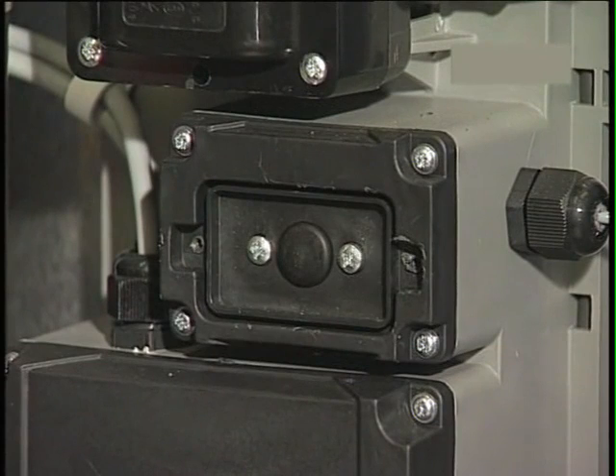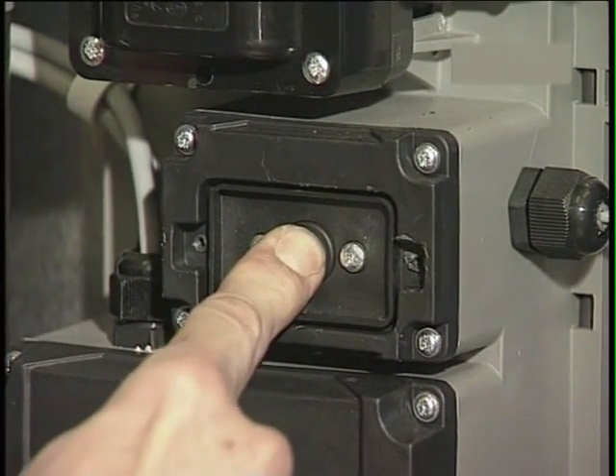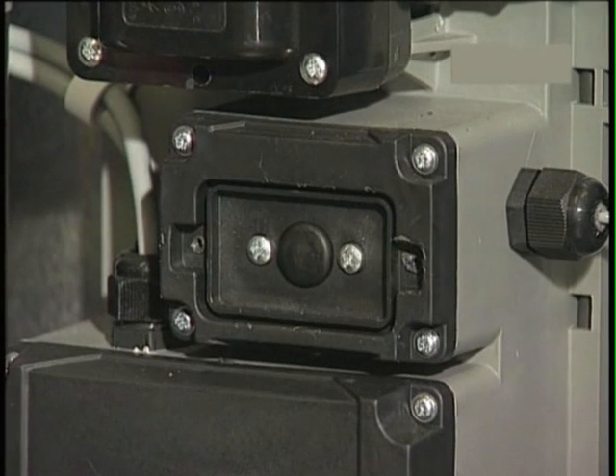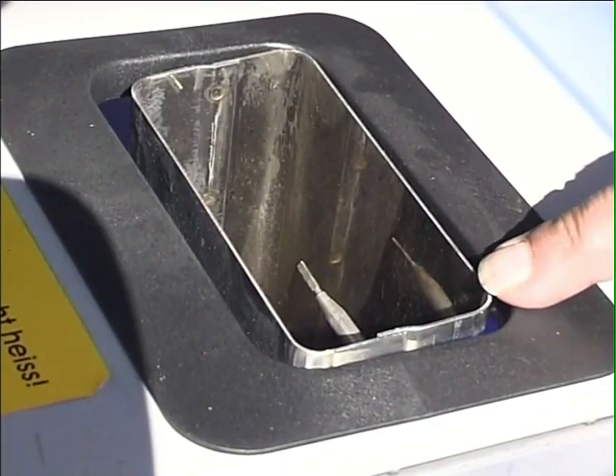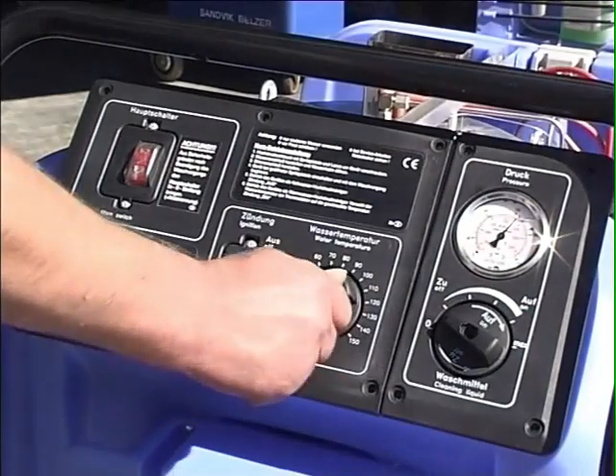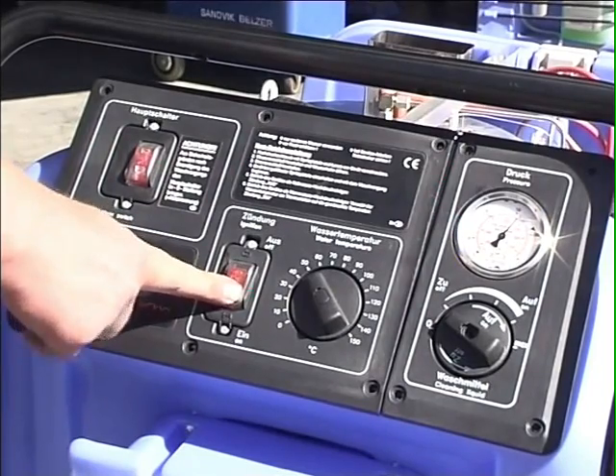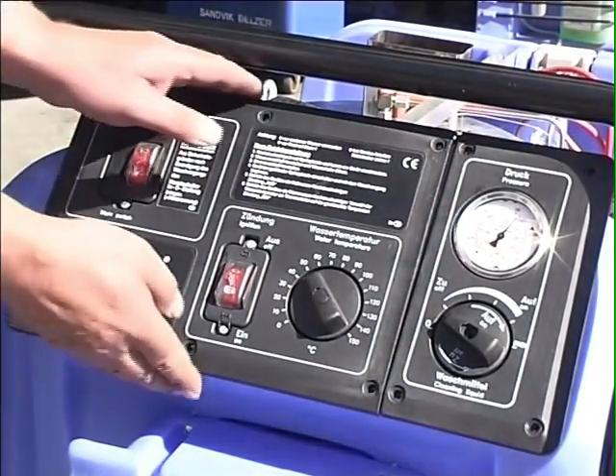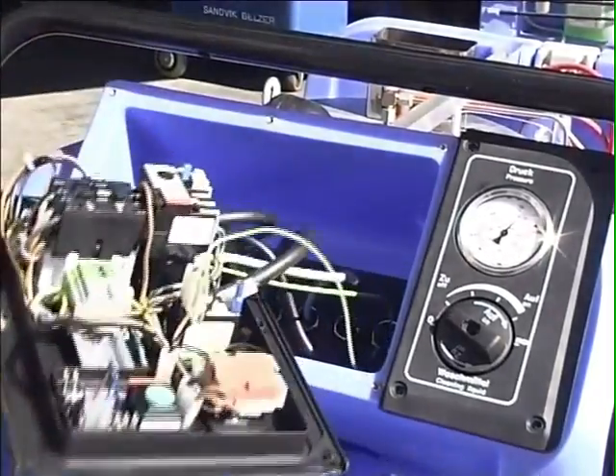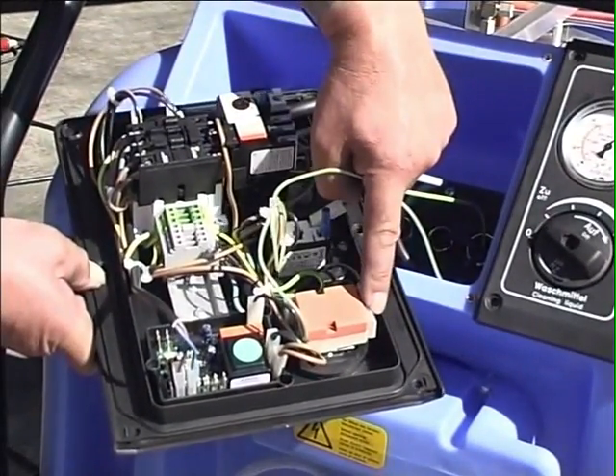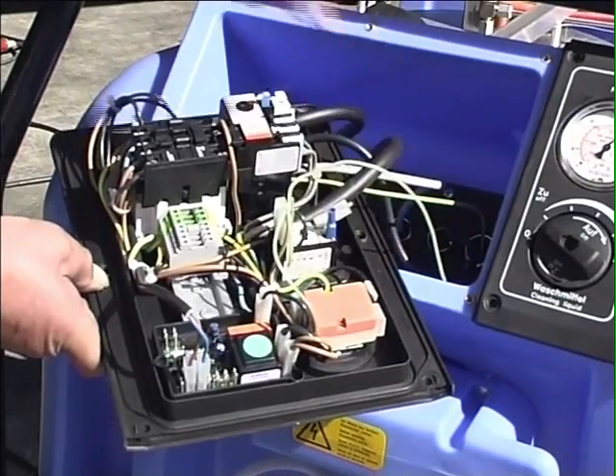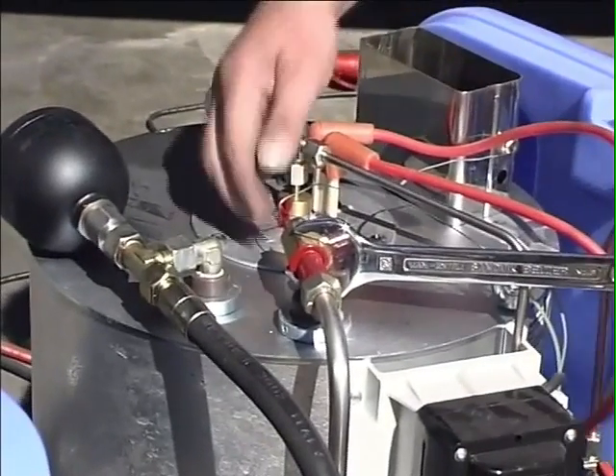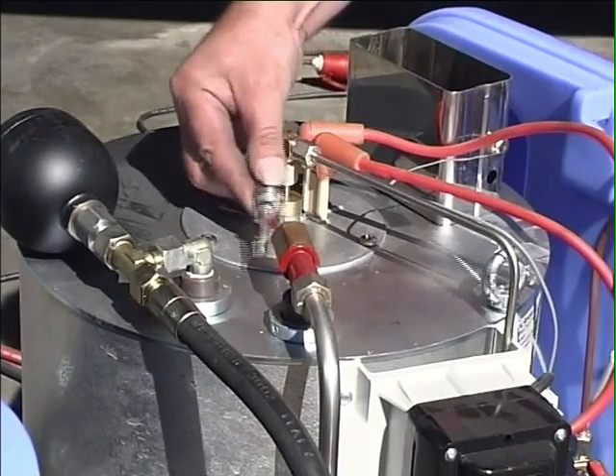This waste gas excess temperature release is activated at 240 degrees Celsius, among others when the heating coil is calcified or full of soot. Normally, the waste gas temperature is 190 to 200 degrees. To start again, please press in again after approximately 10 minutes of cooling time. This probe measures the temperature. If you still cannot switch on the burner, the rotational thermostat is defective. Make sure that these 2 terminals are sufficiently tight. Or check the temperature probe by supplying external heat. You may have to replace it.